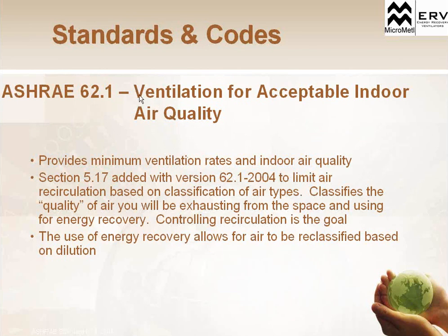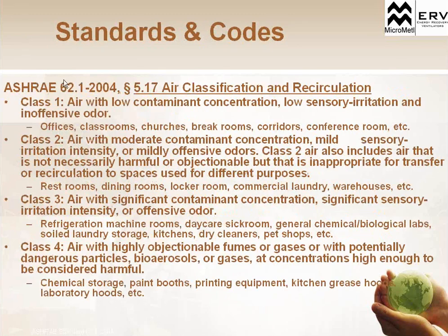Obviously, we mentioned ASHRAE 62.1. This is going to regulate the ventilation requirement for acceptable indoor air quality. So this is what's going to dictate how much outside air you have to bring in. It'll tell you your minimum ventilation rates for your indoor air quality. It's going to classify the amount of air that you're exhausting from the space and when you can use the energy recovery ventilator. And then you can use the energy recovery, which allows your air to be reclassified based on dilution. So they've classified air in a few different ways.